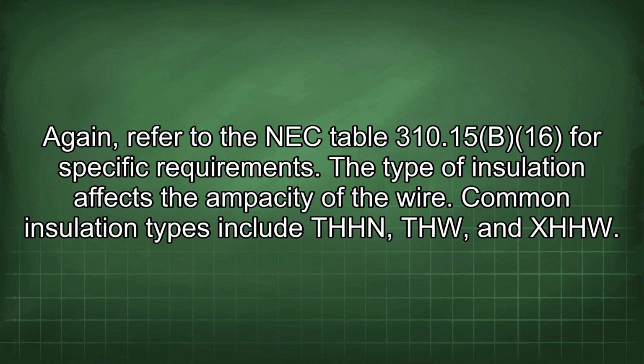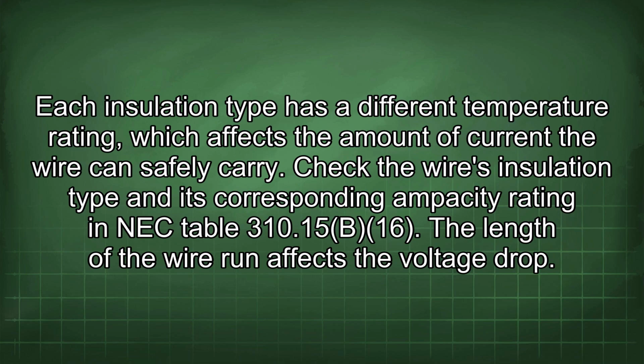Common insulation types include THHN, THW, and XHHW. Each insulation type has a different temperature rating, which affects the amount of current the wire can safely carry. Check the wire's insulation type and its corresponding ampacity rating in NEC table 310.15(B)(16). The length of the wire run affects the voltage drop.